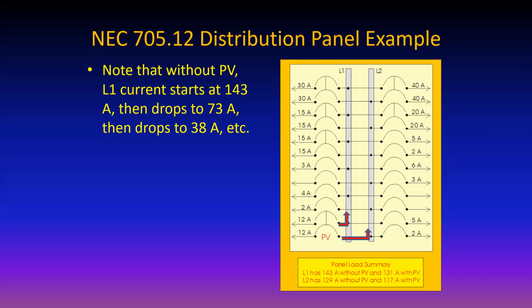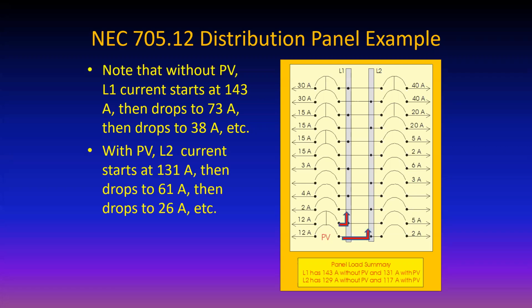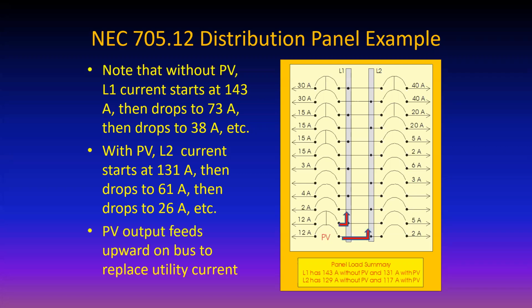And many of you may have, I can remember going into more than one place and putting my hand on the panel above where the main comes in and feeling heat, opening that panel cover, and sure enough, there's a bad connection that got hot. So the less current, the less I²R heating, the better the performance of the panel. So people who say, oh, PV messes you up. No, sorry guys. PV is good for your panel distribution, because it actually reduces the total amount of current required by L1 or L2. And this is all in 705.12.